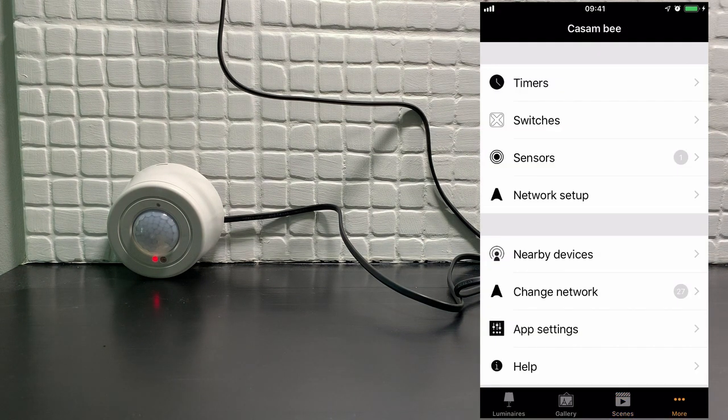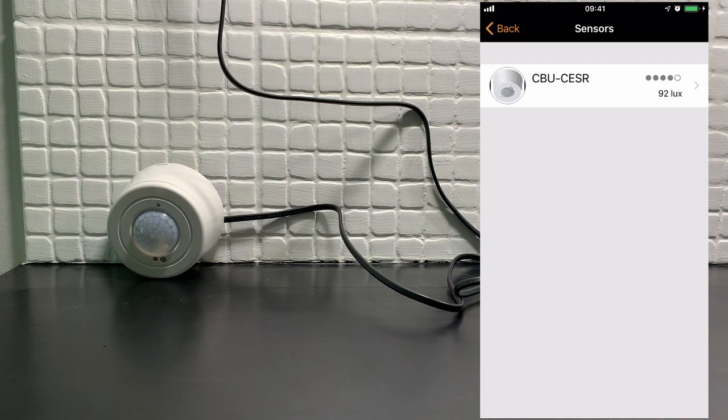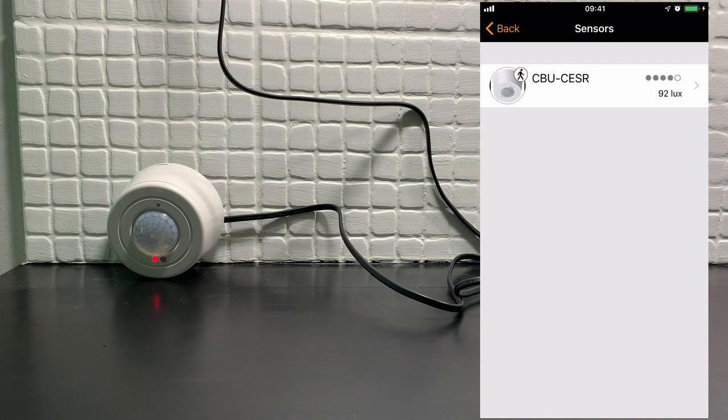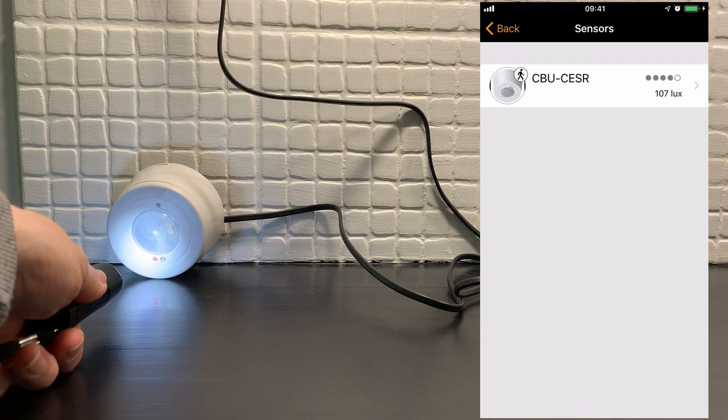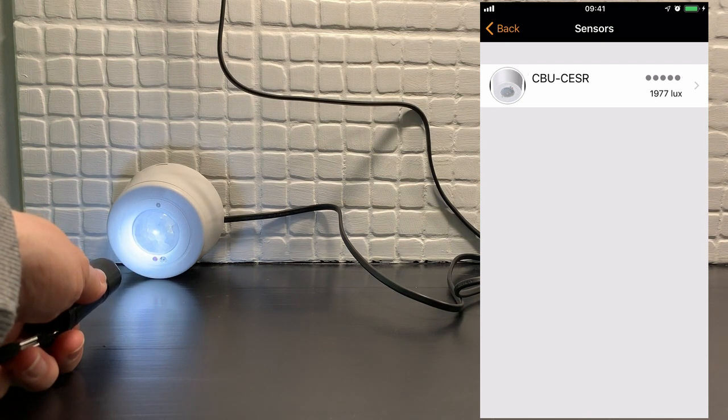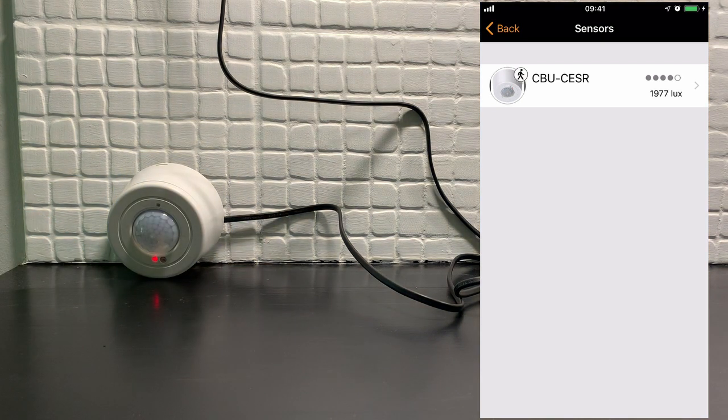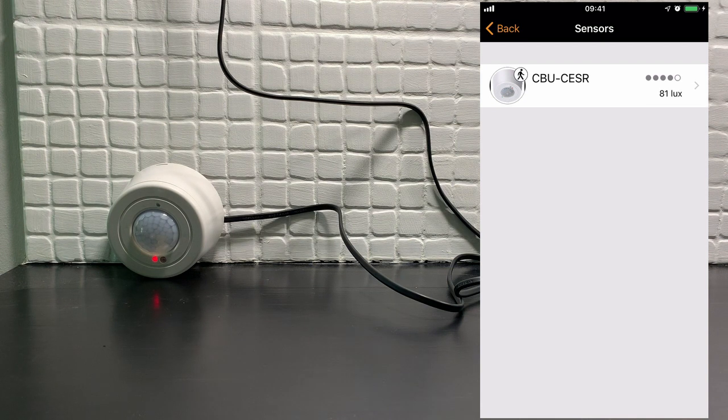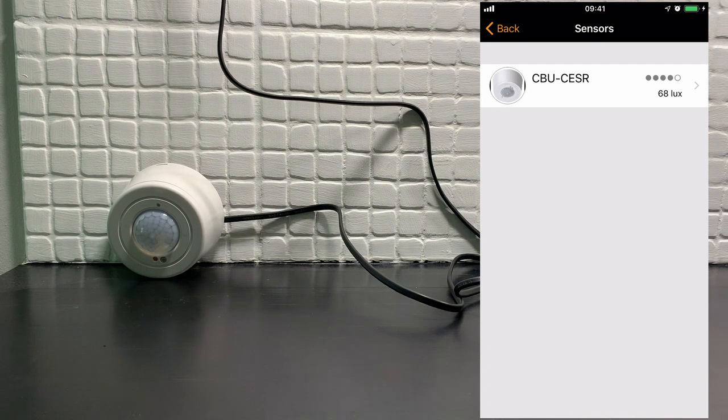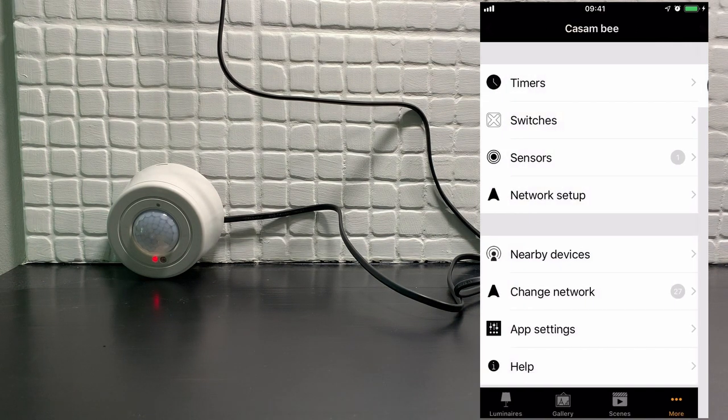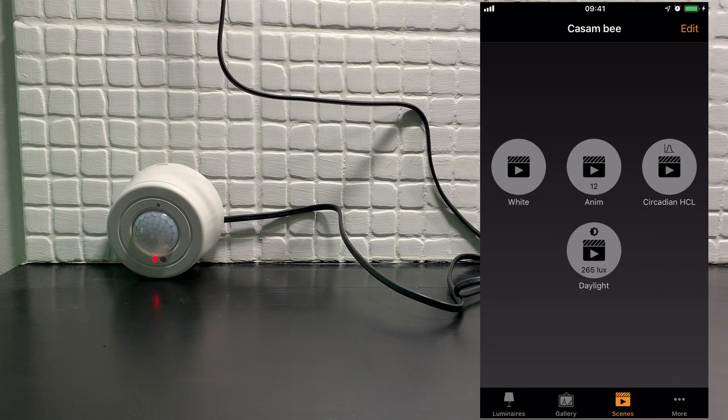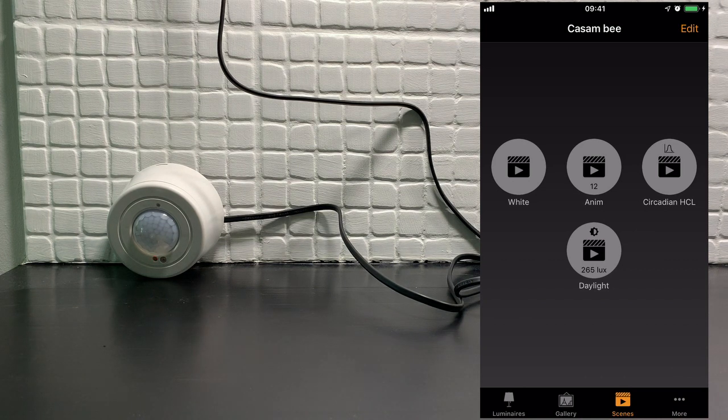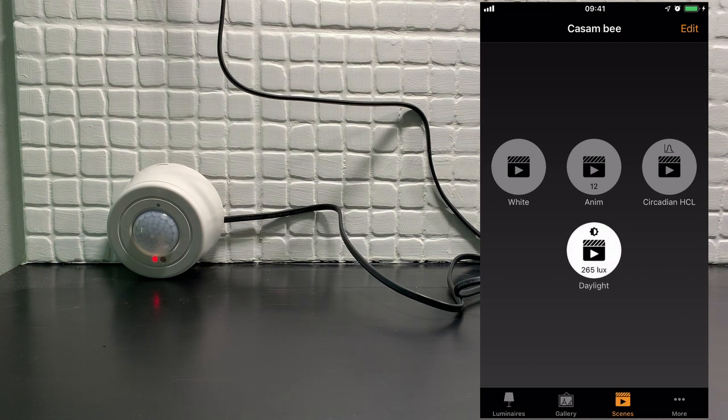So let's look at the input for our sensor now. The sensor is currently reading 92 lux. Again, if I shine a light on it, it jumps to almost 2000. If I take the torch away, it's reading 75 or 68 lux, which means considering that we have set our daylight scene that we requested 265 lux, it should turn all the lights on.